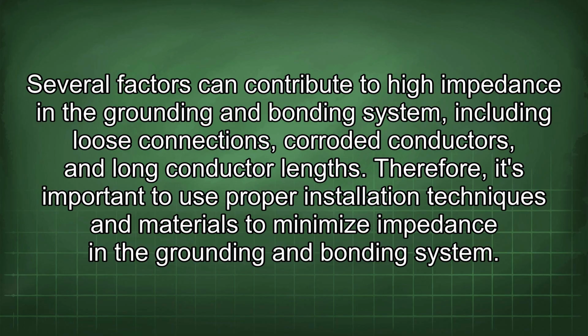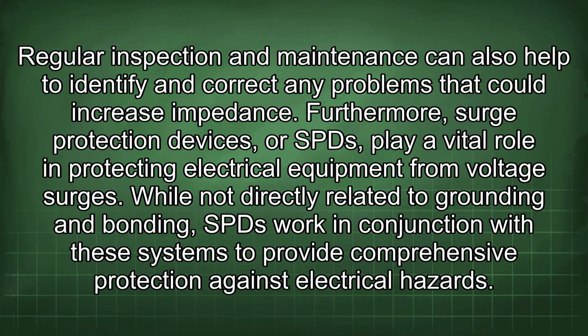Several factors can contribute to high impedance in the grounding and bonding system, including loose connections, corroded conductors, and long conductor lengths. Therefore, it's important to use proper installation techniques and materials to minimize impedance in the grounding and bonding system. Regular inspection and maintenance can also help to identify and correct any problems that could increase impedance.